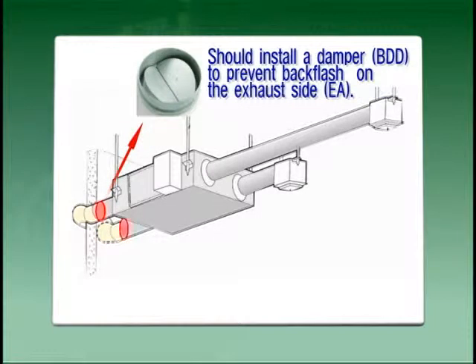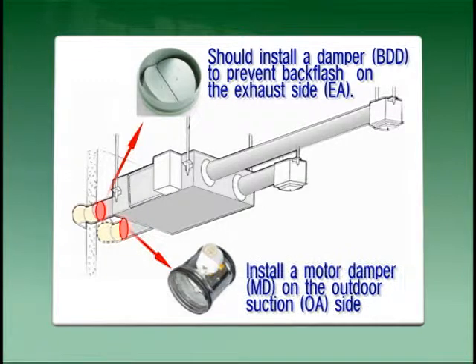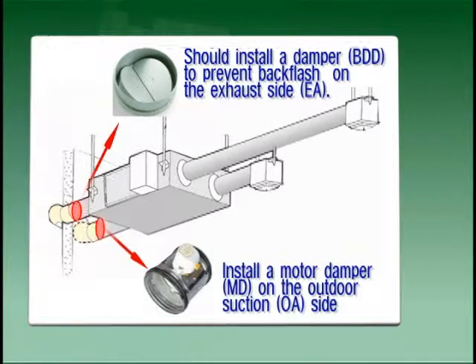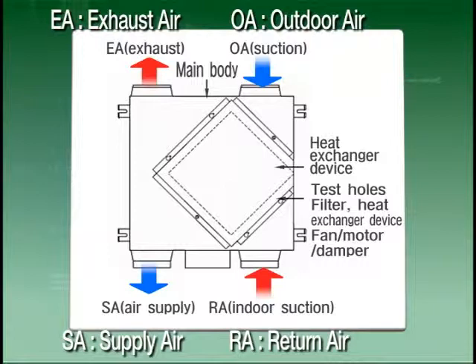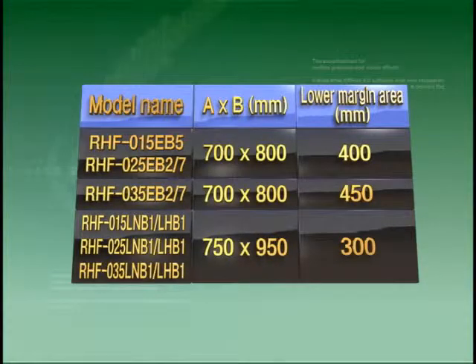When an ERV is installed indoors, an MD and BDD should be located on the OA-EA sides. When installed outdoors, they should be located on the SA-RA sides. If you expect severe condensation in the installation location, then install your MD and BDD on the OA, EA, SA, RA sides and insulate the equipment.